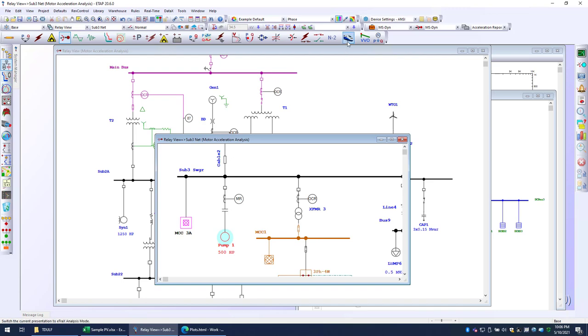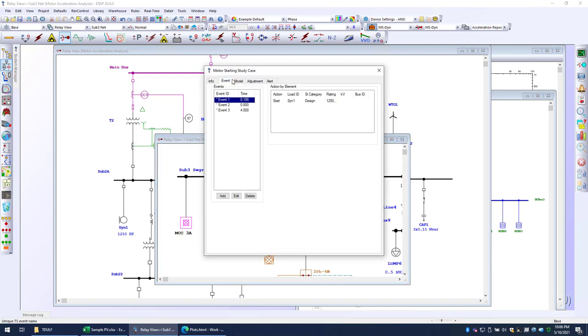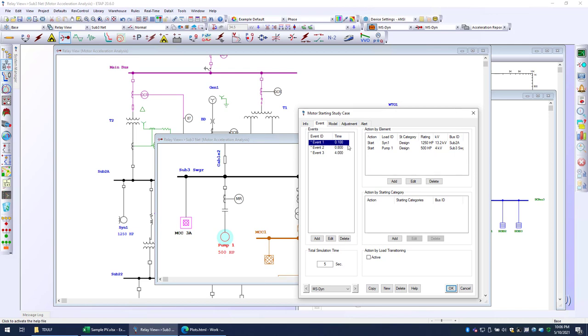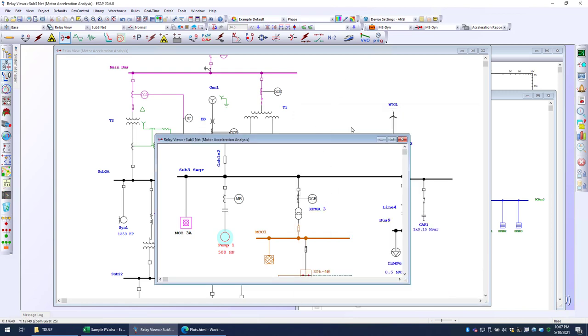So going back to the simulation, I'd like to open the study case and show you the events that are going to take place. There are three events. At 100 milliseconds, we're starting two motors, a synchronous motor and pump number one, which is what we're seeing here. 700 milliseconds later, or 800 milliseconds total, we're going to bring a static load online. Then at 4 seconds, we're going to start one more low voltage motor connected to a 480 volt location. It's 200 horsepower, and the total simulation time is going to be 5 seconds. After we set up the study case with the events like that, we're going to click on Run Dynamic Motor Starting.